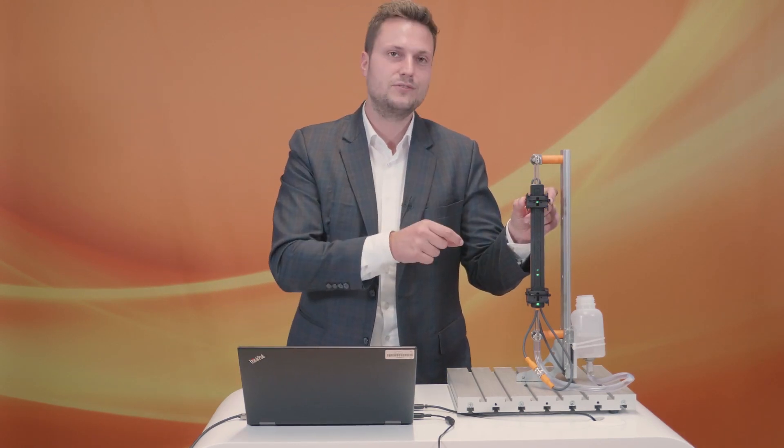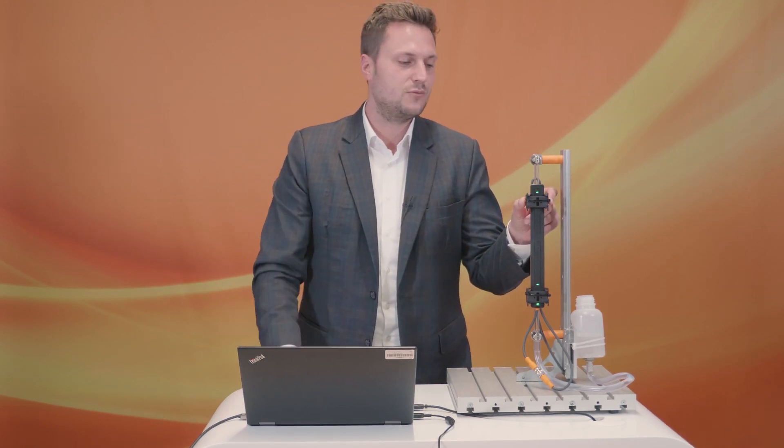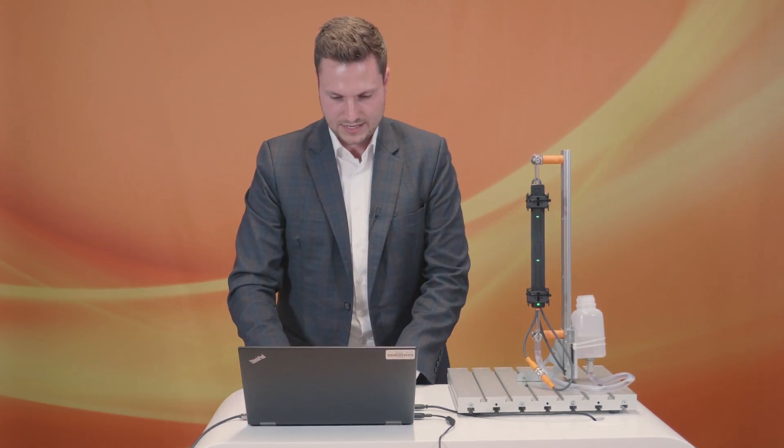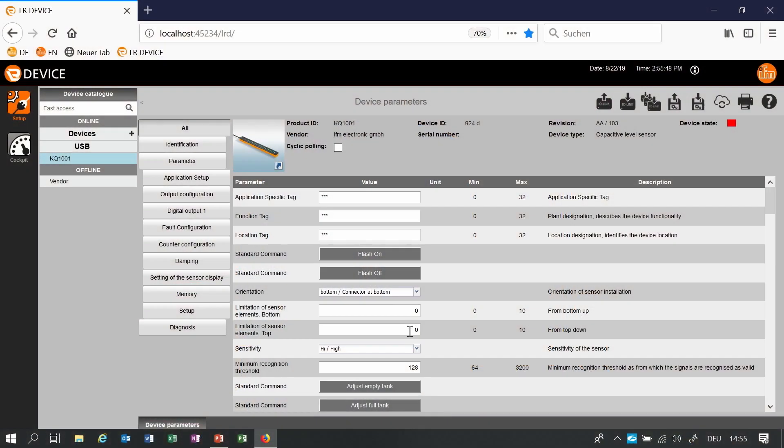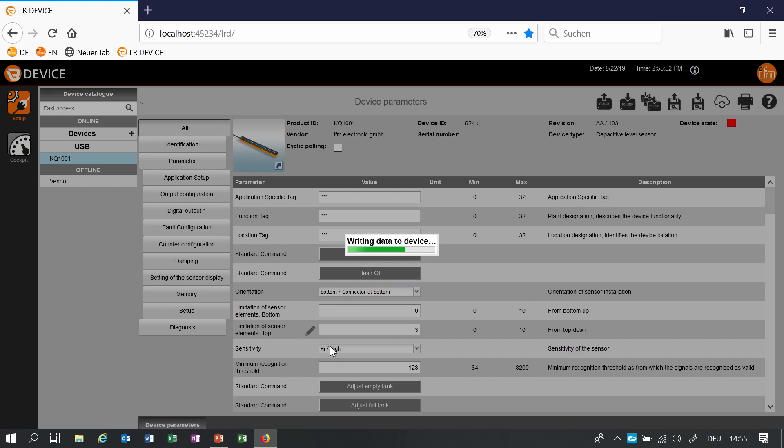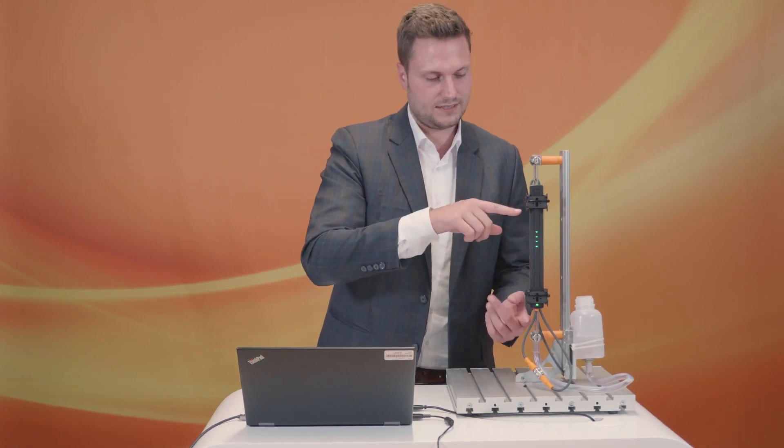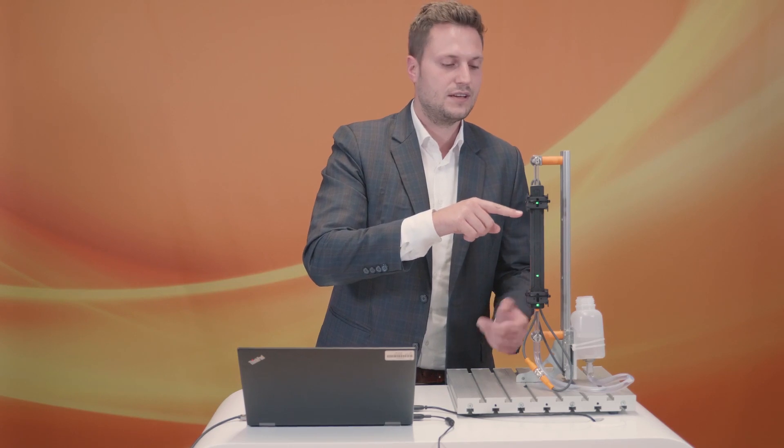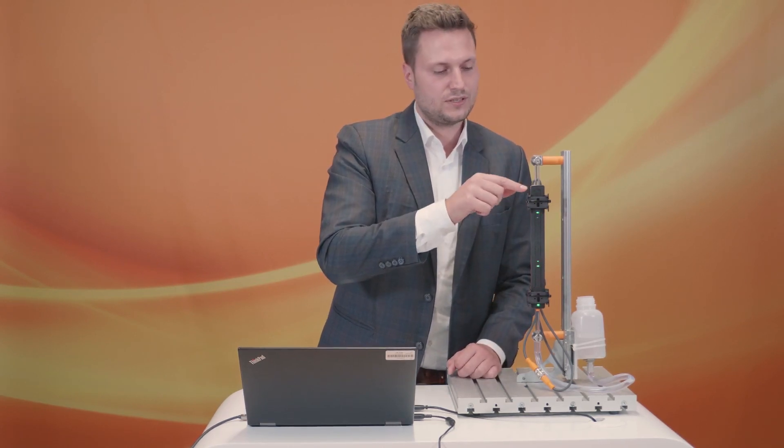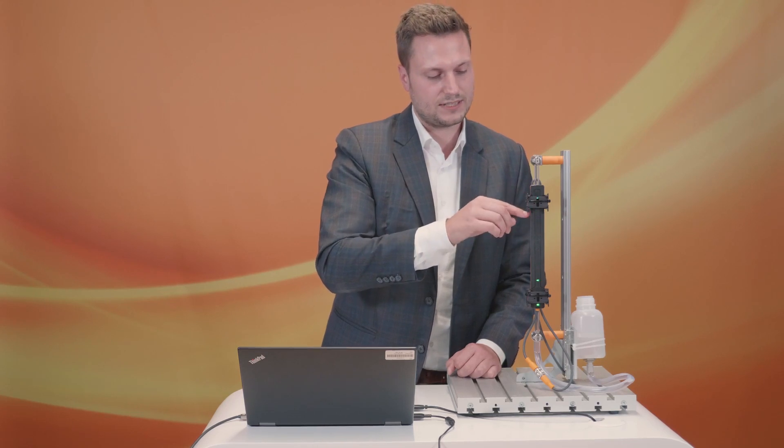We are also able to minimize the detection zone of the sensor. On the sensing face you can see 16 parts of electrodes and we are able to minimize it from the top and the bottom. I will minimize three electrodes from the top. This is good for mounting the sensor when you have just something like a sight glass and the sight glass has just this size. So we are able to minimize the detection zone. So here could be metal and you are able to detect the medium inside of the tank in this area.